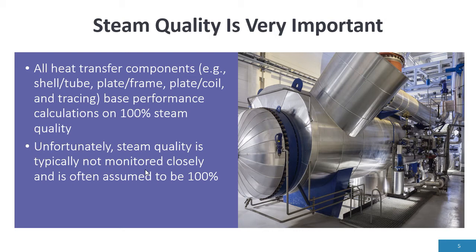Heat transfer components — plate and frame, plate coil, tracing — base their performance calculations on 100% steam quality. Everything is based on 100% steam quality. Unfortunately, steam quality typically is not monitored closely, or not even monitored in plant operations, and we always assume it's 100%. The steam coming off a saturated boiler is not 100% — it's close, maybe 98.5% or 99%, but not 100%. As steam travels through the system, steam quality will start to degrade, and that's why we need to know what quality the steam is at.